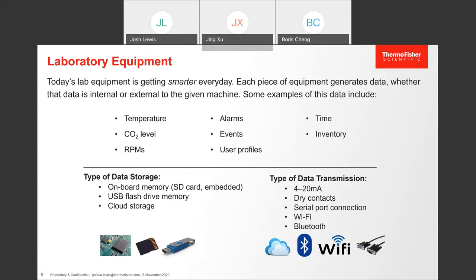Outside of storage, data goes through a transition: generation, then it gets passed, then ultimately stored. There are many different types of connection points on laboratory equipment. Some of the more basic connection points being 4 to 20 milliamp or dry contacts. These are historically the most common when accessing a single piece of information, whether that's temperature via the 4 to 20, or an alarm state from the dry contacts.